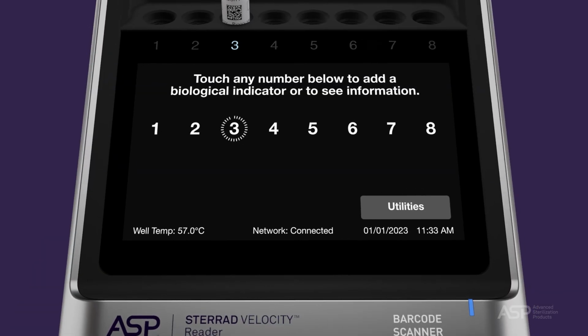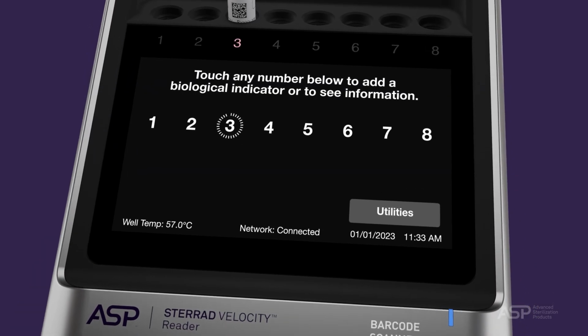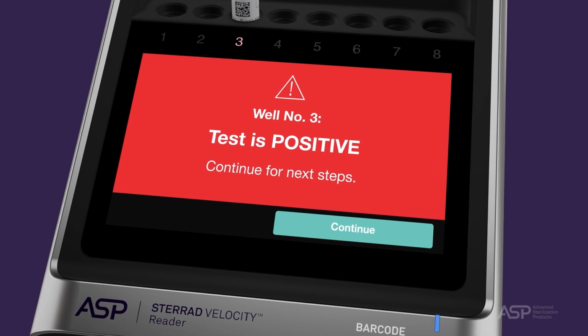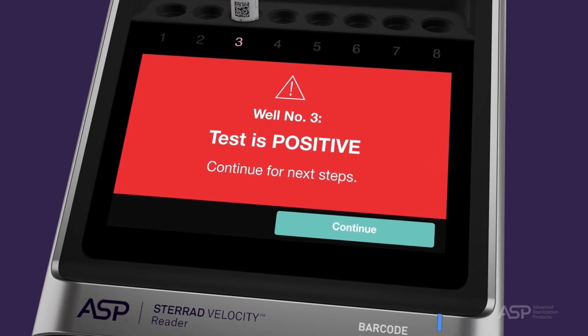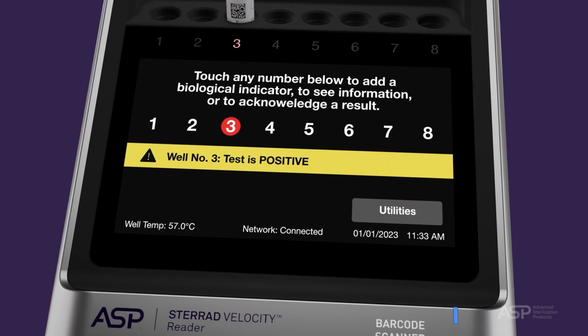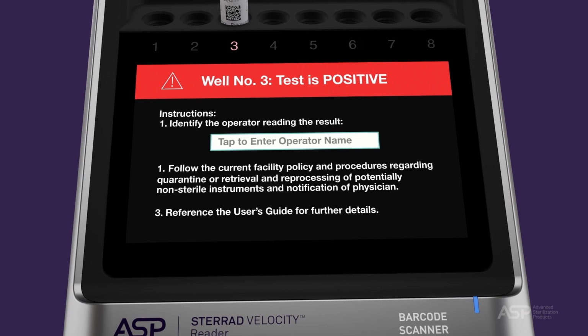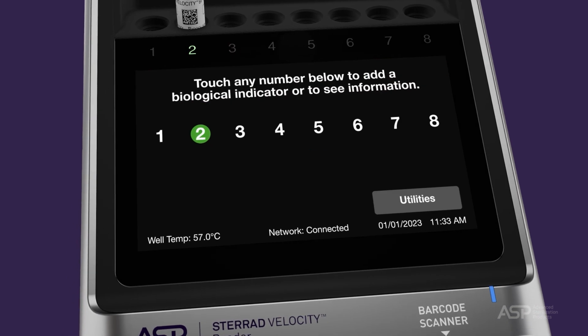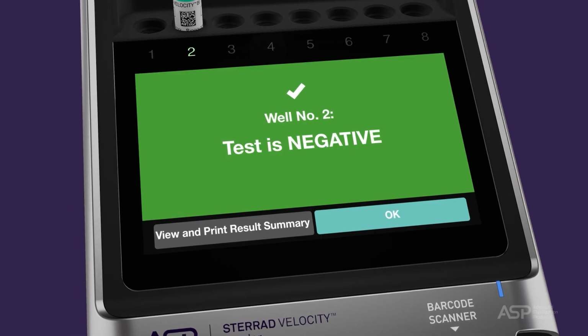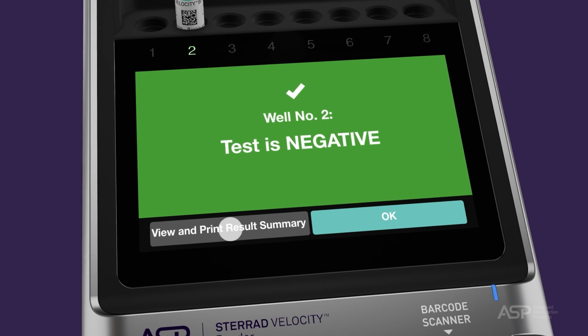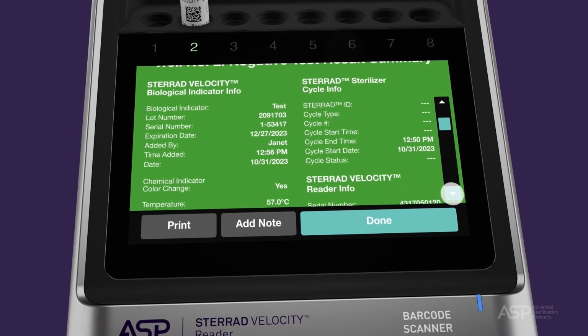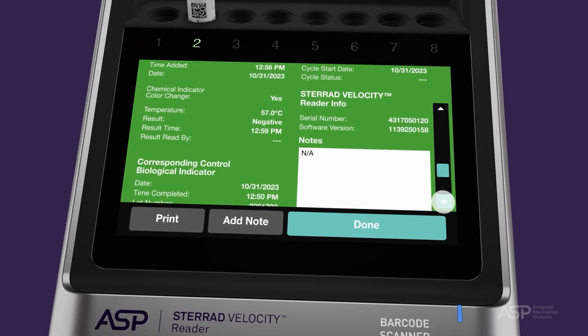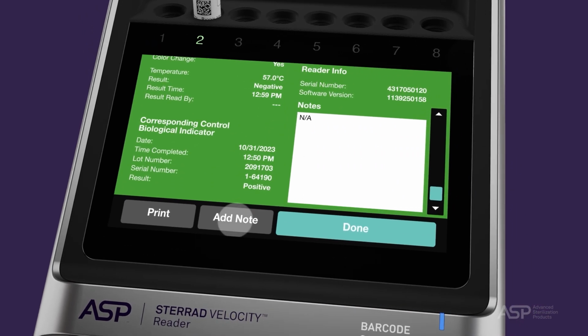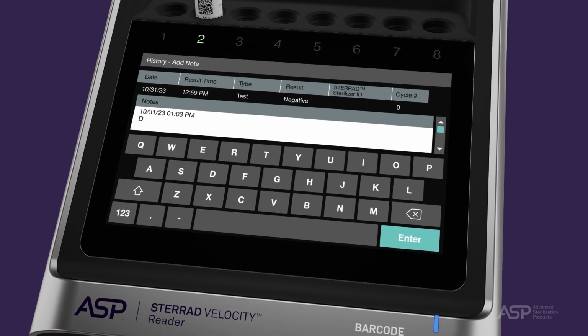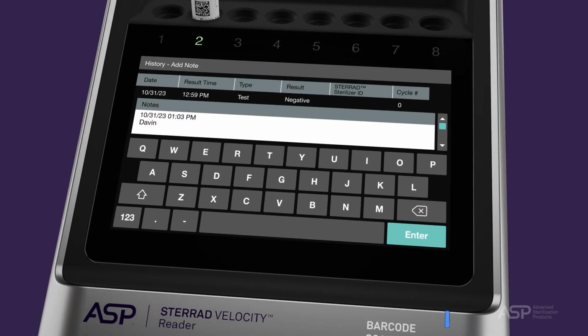The system will ask the user to contact an ASP representative if the reader detects 2 out of 3 test biological indicators are positive. You will continue to receive this warning after each sterilization cycle completion until 2 consecutive STERRAD Velocity Reader test BIs are negative. For detailed information on interpretation of results, please review the instructions for use included with the biological indicator and the STERRAD Velocity Reader User's Guide.